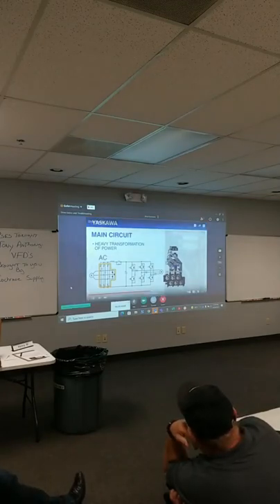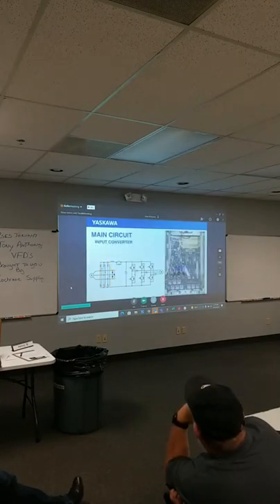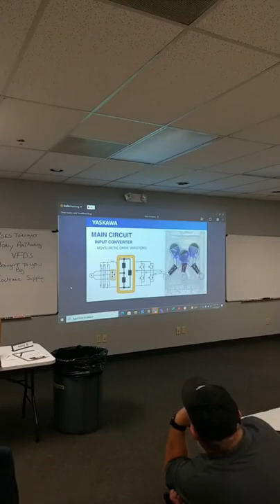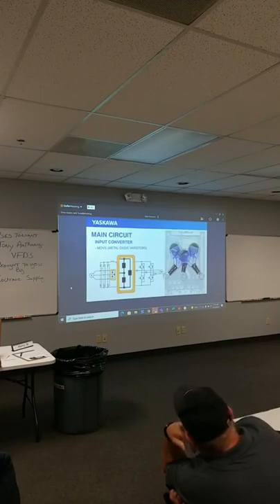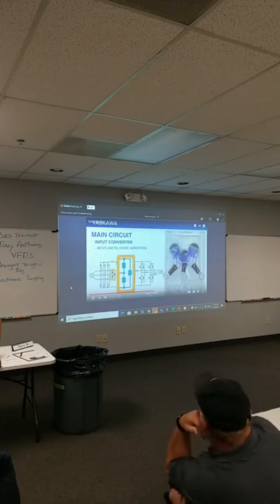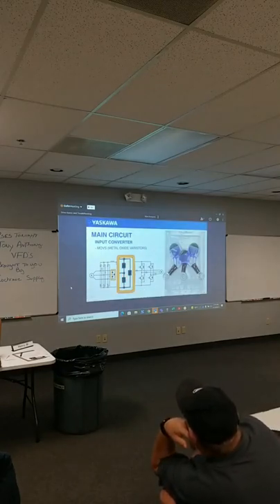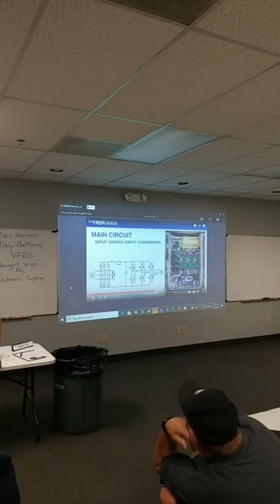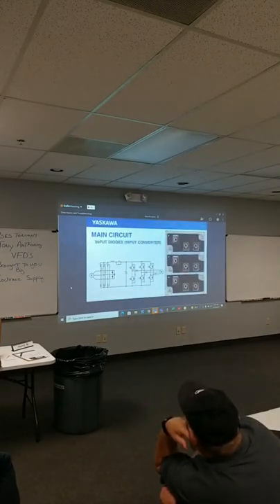Starting at the input of the drive, the first device that the incoming line will see is the MOVs, or metal oxide varistors. These resistors are in place to take on any incoming voltage transients or spikes, such as switching transients associated with relay and contactor energization and de-energization. When these resistors come into contact with a high spike, they allow the spike to bleed off to another line and travel safely back out to the incoming line, thus suppressing the spike and protecting the more expensive components in the drive. Well, this brings us to the input diodes, or input converter, commonly known as the rectifier.